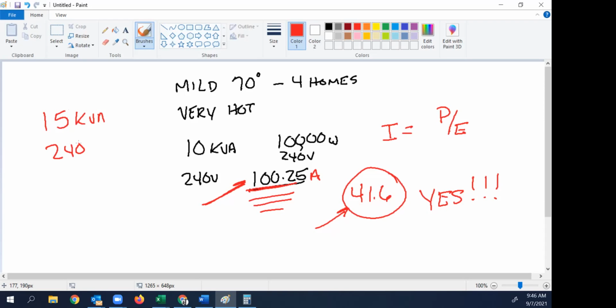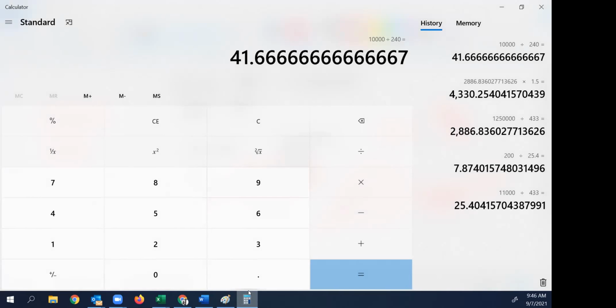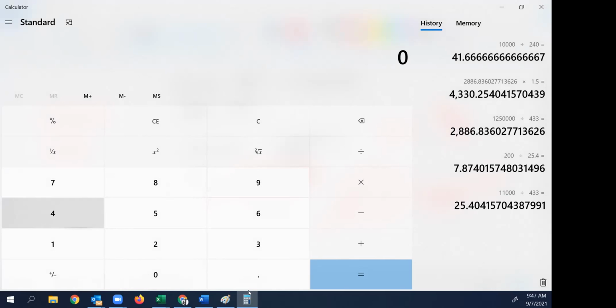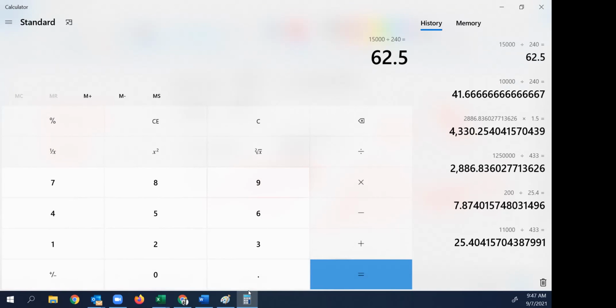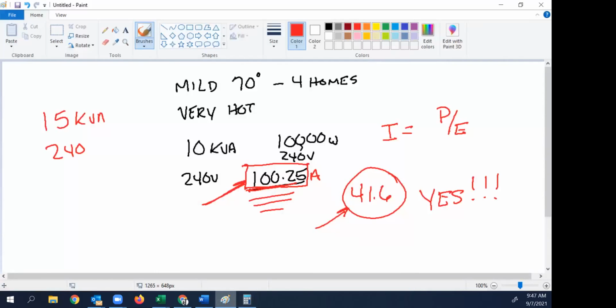Now we've got to remember this number right here, we want to at least cover 100.25. So back to the calculator: clear this entry, 15,000 divided by 240. Uh-oh, that's 62.5. That's not going to cover the 100.25. That's not going to make it.